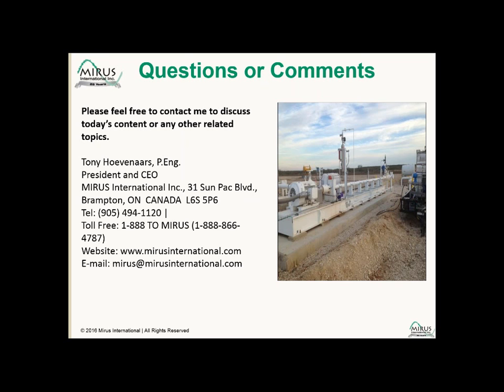Is the oversizing just on the component of the load that's nonlinear, or oversizing of the peak estimated load? Very good question. I believe it's on the total capacity of the generator and the total size of the load. So if you have 25% or higher nonlinear load and the generator manufacturer recommends that you oversize, you need to oversize relative to your total load.